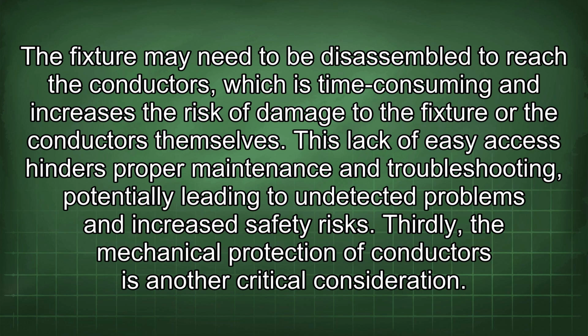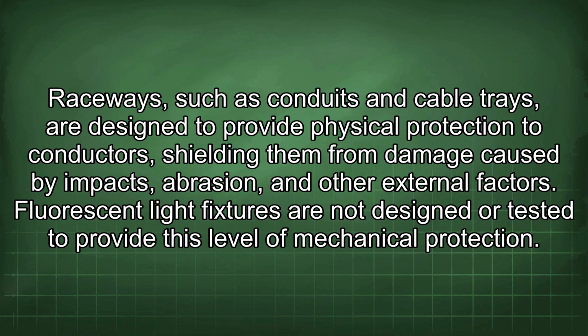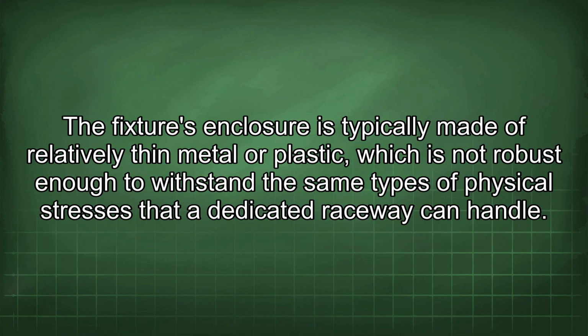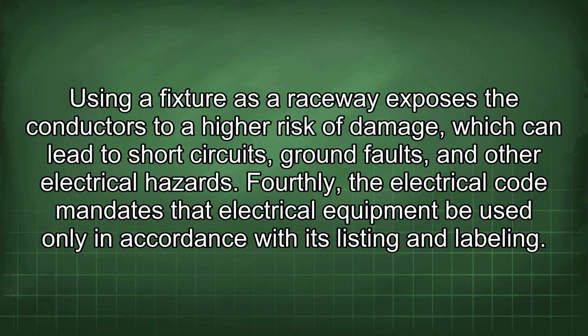Thirdly, the mechanical protection of conductors is another critical consideration. Raceways, such as conduits and cable trays, are designed to provide physical protection to conductors, shielding them from damage caused by impacts, abrasion, and other external factors. Fluorescent light fixtures are not designed or tested to provide this level of mechanical protection. The fixture's enclosure is typically made of relatively thin metal or plastic, which is not robust enough to withstand the same types of physical stresses that a dedicated raceway can handle. Using a fixture as a raceway exposes the conductors to a higher risk of damage, which can lead to short circuits, ground faults, and other electrical hazards.